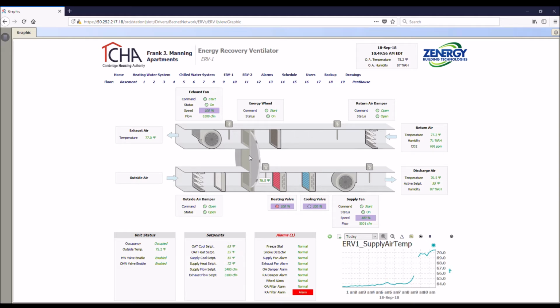Like I said, the wheel just operates all the time. It's not a heating or cooling wheel, it's really based on what season we're in. So if it's hot outside, if it started to get hotter here, we have this hot stream of air coming in here, but we're trying to get a 55-degree air set point. So the idea is to take some of that heat, transfer it onto the wheel, and cool the wheel using the cooler return air. I guess, like I was saying, right now our return and our outside air are pretty much identical.